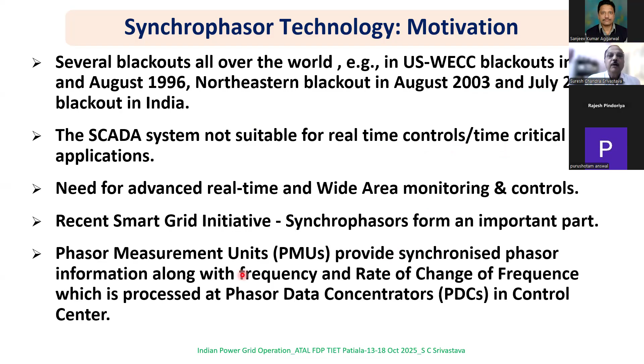Whereas with the synchrophasor system, the base unit is the PMU, phasor measurement unit, where you take CT and PT data and generate current and voltage phasors. This is directly transmitted to a phasor data concentrator at the control center, where it is time-aligned. In fact, the PMU needs time data, which comes from GPS.